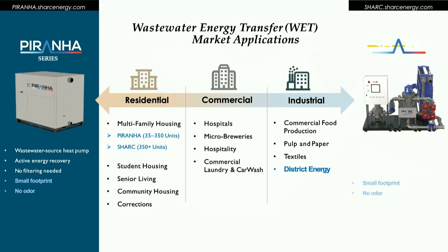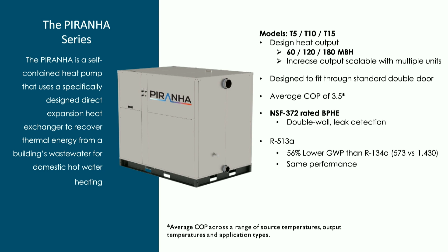I won't hit every point on these slides due to time, but I included them in the deck since you'll have a copy to look at later. On the Piranha unit, there's a source and a load. The load side delivers basically 140-degree potable water, and depending on the source temperature, that can be 3.5 COP — 350% more efficient than an electric boiler — up to 5.5 or 6 COP depending on source temperature. It's a double-wall vented heat exchanger, NSF rated for potable use, so it can take any kind of effluent or wastewater and deliver 140 degrees.